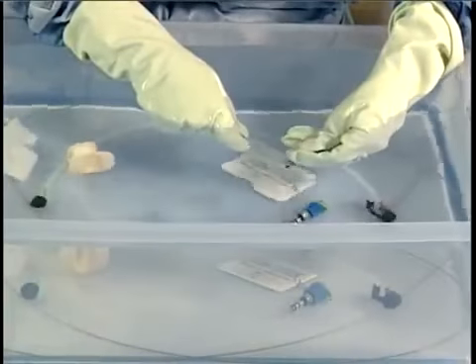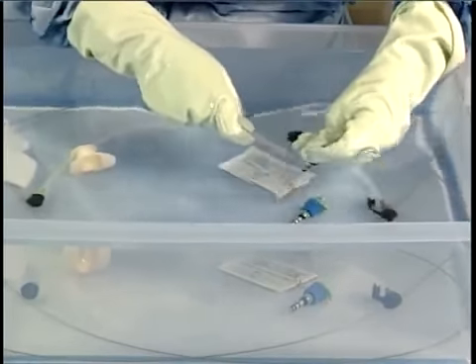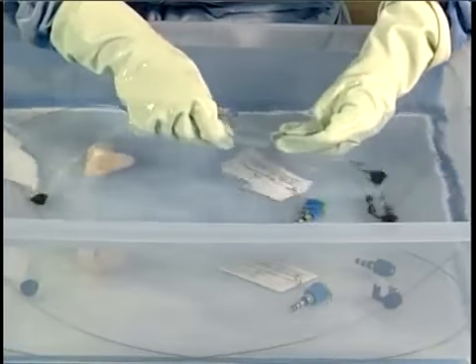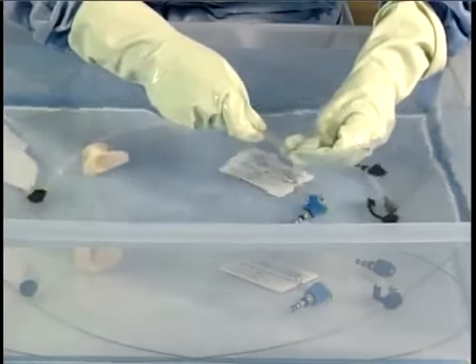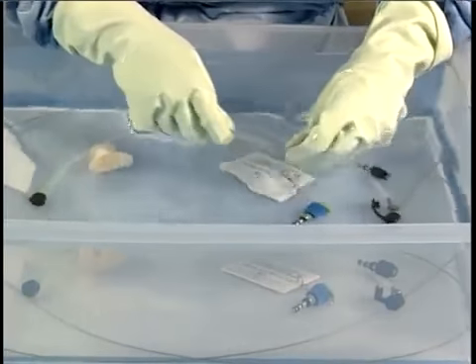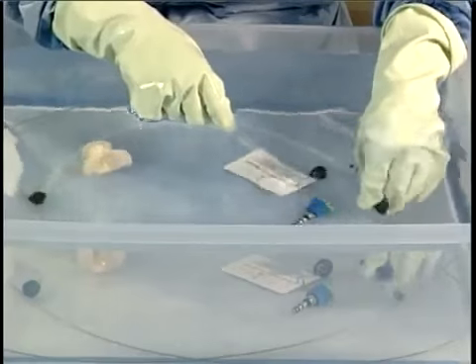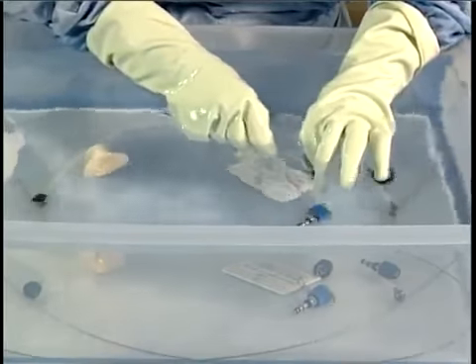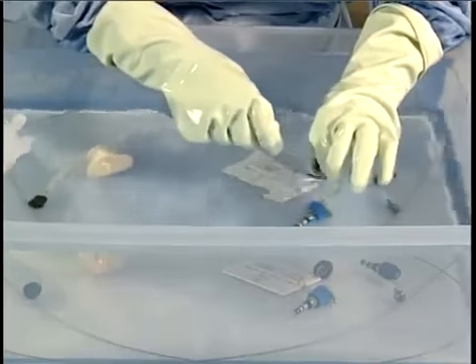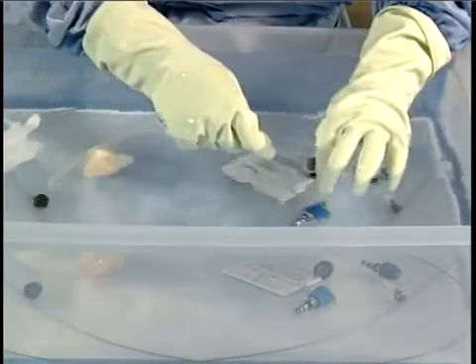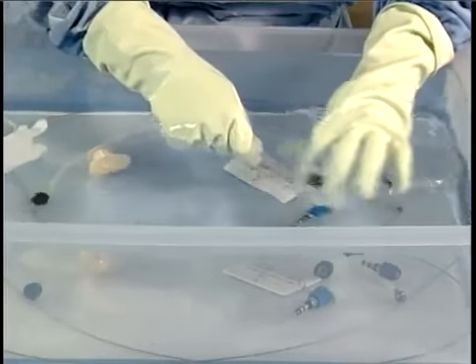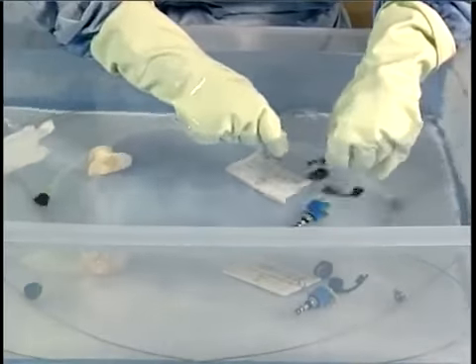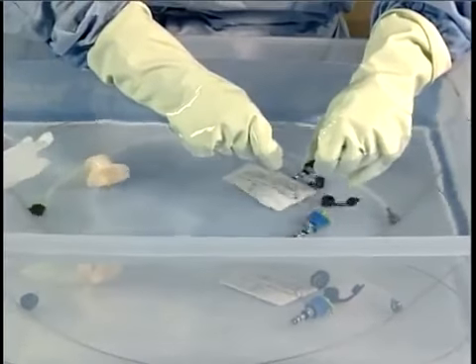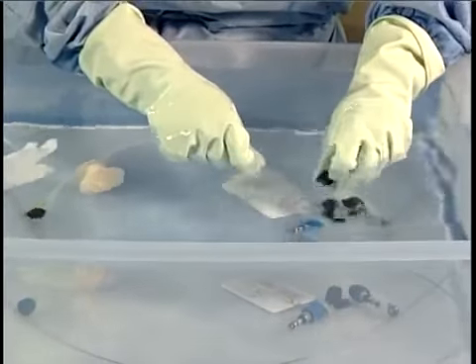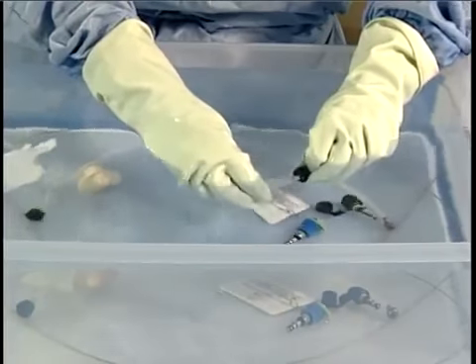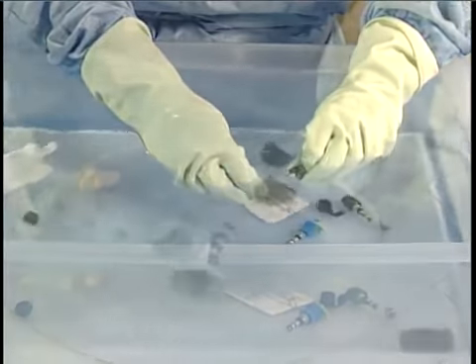While immersed, depress and release the pistons of the air-water valve, the suction valve, and the air-water channel cleaning adapter to ensure the detergent solution contacts all crevices. Use the channel cleaning brush to thoroughly brush the openings of the suction and air-water valves and the air-water channel cleaning adapter. Be careful not to scratch the valve seals with the brushes. Continue brushing until there is no visible debris. Clean all brushes while immersed in the detergent solution.